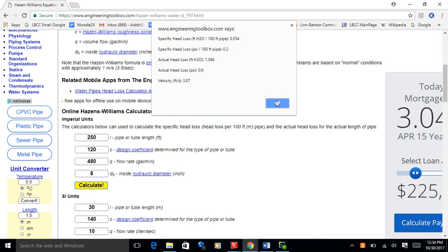Well, try and get the pump about right. I'll oversize it a little bit is what I'll do, because I'll figure as the system ages, it'll have to push against more head loss. Goldilocks. Yeah, right. Sometimes the inclination is I'll just put a really huge pump in there, but that may not work well, depending on what you're trying to do. Okay. So why don't you guys do the one on page 111.